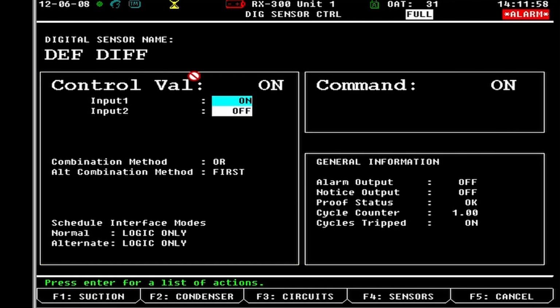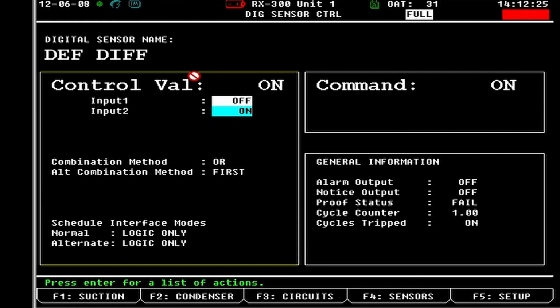So if both suction groups were to call for the defrost differential valve to be on, it would be on. If one suction group calls for it to be off and the other one's on, it's going to be on. So if they both call for it to be off, it's going to be off. See, it's still on. See, and then we have a cycle counter. So it's cycled one time.